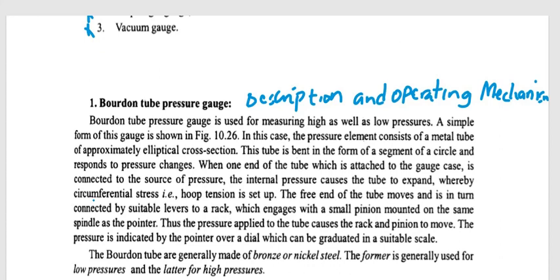To begin with is the Bourdon tube pressure gauge, which is used for measuring both high and low pressures. A simple form of this instrument has a pressure element consisting of a metal tube of approximately elliptical cross-section, bent in the form of a segment of a circle. In response to pressure changes, when one end of the tube is connected to the source of pressure, the internal pressure causes the tube to expand, whereby circumferential stress — in other words, hoop tension — is set up.